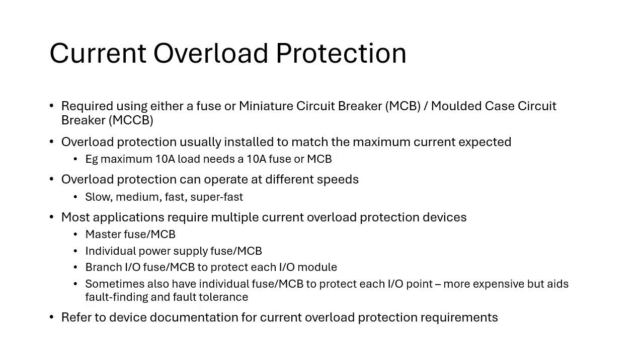Most applications do require multiple current overload protection devices. So you'll typically have a master fuse on the main power supply. Then you'll have individual power supply fuses to each power supply if you've got more than one. And then you'll have branch I/O fusing that can protect each individual component or I/O module. And it's possible, depending on how much fault tolerance you've got, but of course it costs more, because the more fuses or MCBs you have, the more money you've got to pay, and also the more wiring there is to do, and also potentially you need a bigger panel.